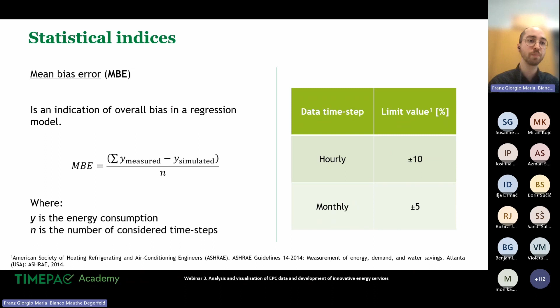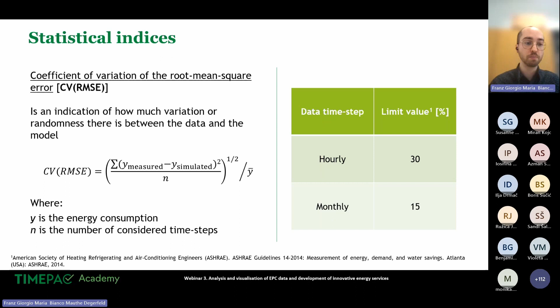So the statistical indices that we're going to use are the mean bias error, which is an indicator that represents the overall bias in a regression of a model. On the right of this slide, we can see some of the limits that are proposed by ASHRAE regarding this value for a calibration procedure. The second statistical index is the coefficient of variation of the root mean square error, which instead indicates how much variation or randomness there is between the data and the model. And again, on the right, we have some limits proposed by ASHRAE.